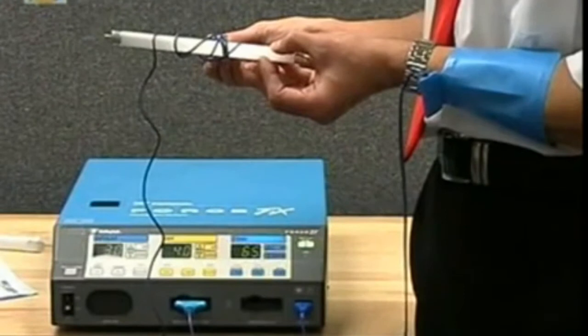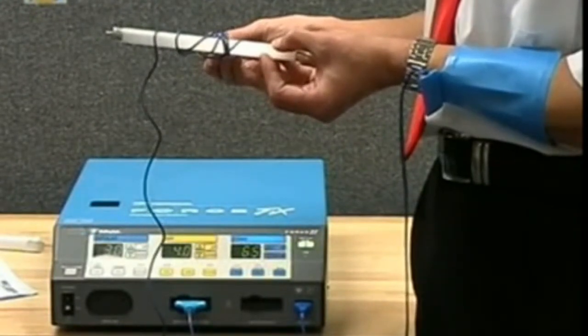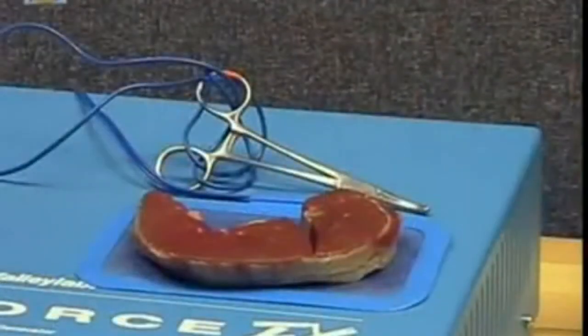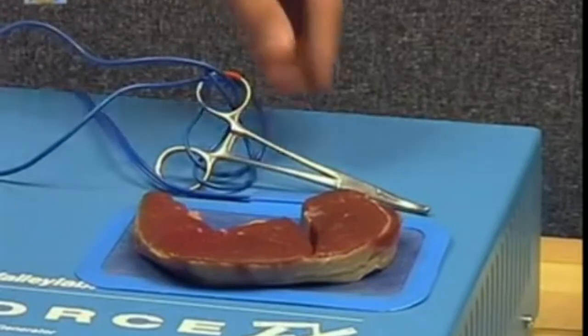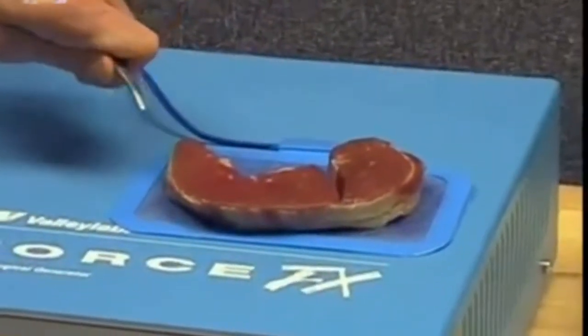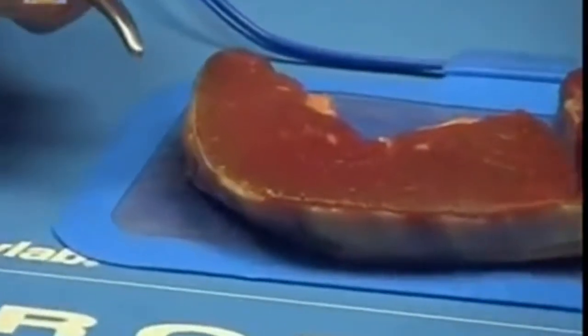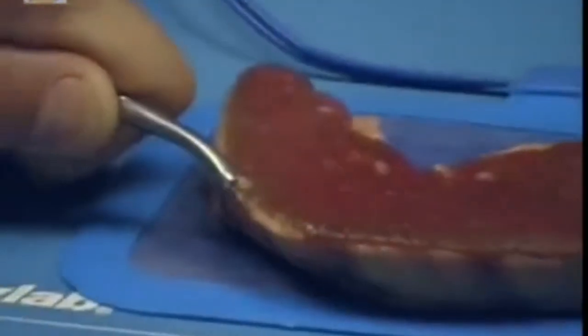You should be aware that due to the high power flow through cables supplying electrosurgical instruments, the phenomenon of current leakage occurs. Here, you can see this leakage current is high enough to light an unconnected fluorescent tube. More worryingly, if electrosurgical cables are wrapped around metal instruments, current leakage will energize the instrument, which, if in contact with the patient's skin, has the potential to cause a burn. A practical example might be the tip of a clip used to secure drapes having cables wrapped around it and then coming into contact with the patient's skin. We demonstrate this here using a pair of forceps and the steak to represent the patient's abdomen.